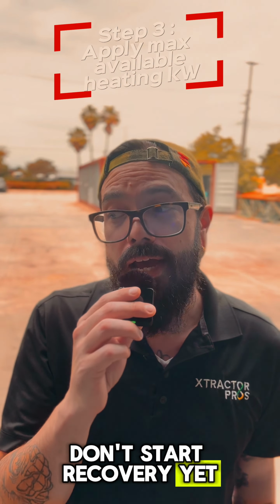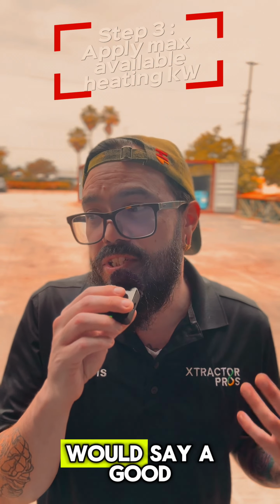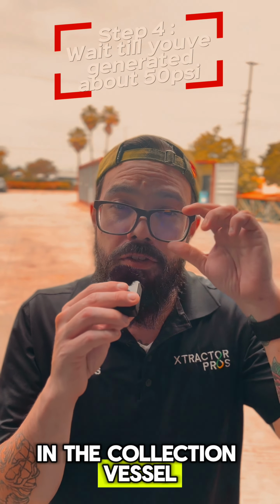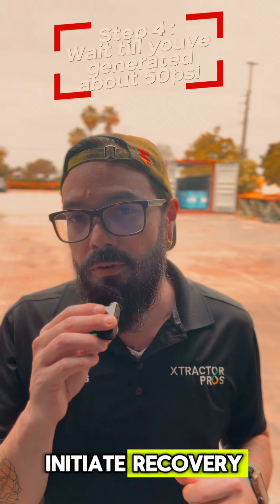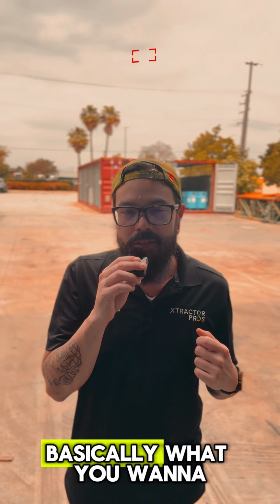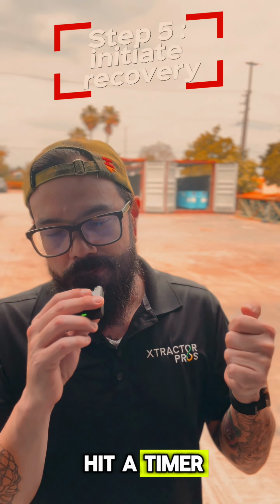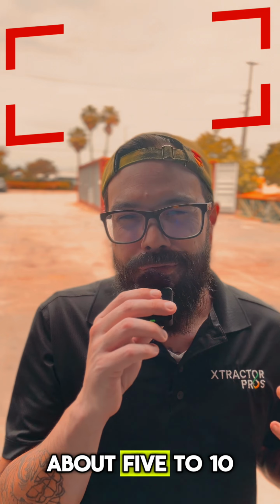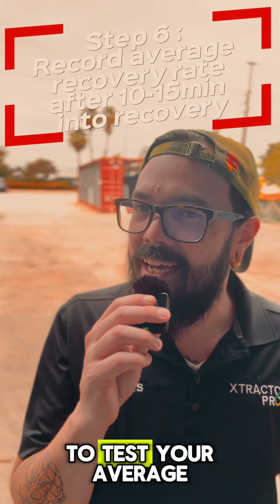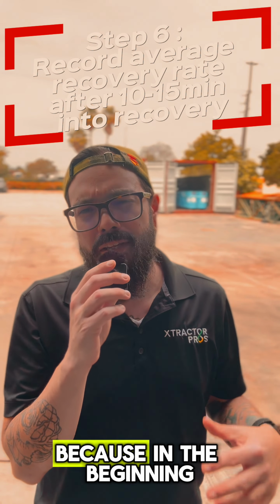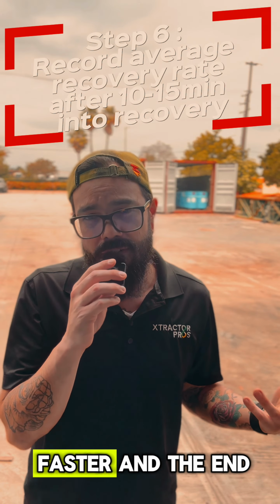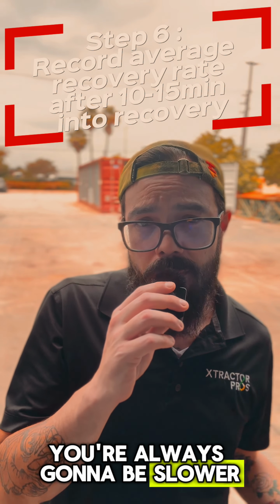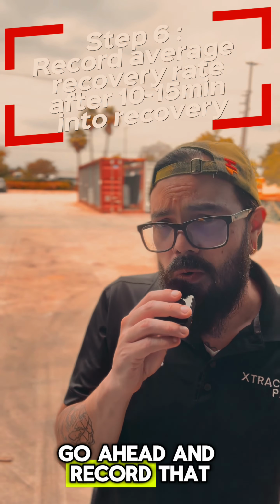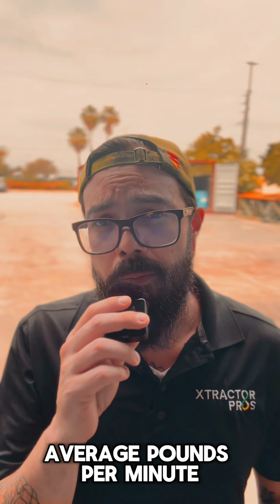Don't start recovery yet. Develop some pressure, I would say a good 50 psi in the collection vessel, before you initiate recovery. Then initiate recovery. Basically, you want to hit a timer and watch your scale. About 5 to 10 minutes in is a good time to test your average recovery rate, because in the beginning of your run you're always going to be faster, and at the end of your run you're always going to be slower because you're lacking pressure. Go ahead and record that average pounds per minute that you're getting.